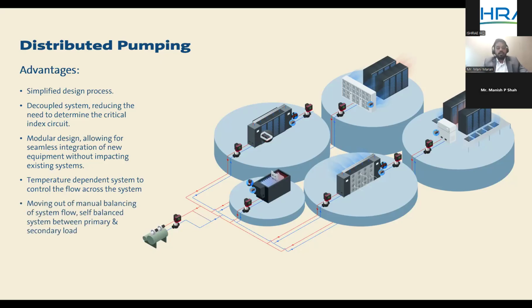And this is something which is very critical. Balancing. Being a closed loop system, centralized pumps need a good balancing approach to make the system efficient. Now, how do we do that? We do that with the help of valves today. We have a balancing valve at each unit level, and we try to balance the flow based on the capacity or the need of that particular unit. What happens if the balancing is not proper in the system? The entire efficiency of the system is compromised. So balancing is always a critical parameter in a closed loop system, and it's not one time. It has to be maintained throughout the operation of the system to make it more efficient and to address the temperature of each unit. This is a little complex, and it has to be managed every time in the traditional way of design. That's what we are trying to address.